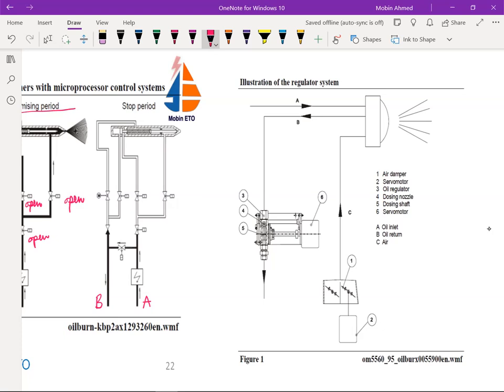So this is a servo motor. 3 is the oil regulator. You can see the oil regulator here. 4 is the dosing nozzle, whereas 5 is the dosing shaft and 6 is a servo motor. So this is how the oil is going back. Okay, oil is going back to this one. Now, sorry, here we are going to have the C. C means the air. So air is going from here to here. It is going to come through the FD fan, and this is the damper, and this is the servo motor for that. You can see as this one is going to open.